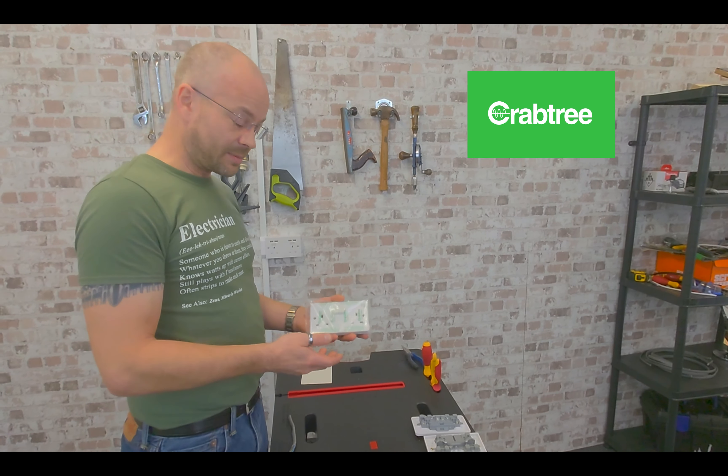Now, see, I've just taken the screw out. So there is one bad thing about these, is because they don't have that stopping lug, you do run that risk. I'll just leave that out for a moment. I'll look at that again in a second. So how does it feel with the cable in there? Well, as you can see, hopefully in the camera again, the nice deep holes. I'm going to put this into the neutral hole, even though I'm going to use the live cable, just to see how deep that is. And that is very decent. There's a decent depth in there.